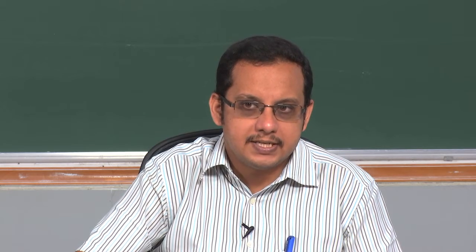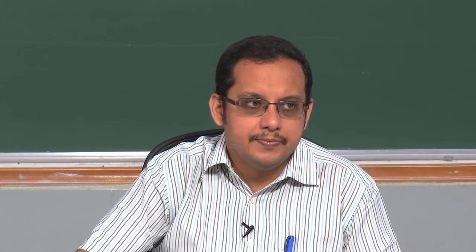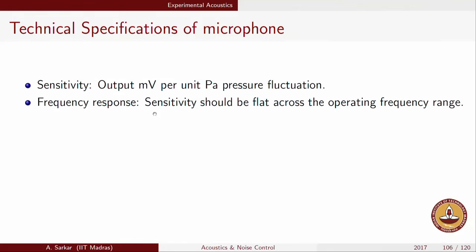Sensitivity is one of the most important factors in selecting a microphone. You need a high sensitivity value, because if the voltage is very low it will be embedded in the electrical noise of your measuring system and will not be properly manifested. Higher voltage gives good signal quality, so higher sensitivity is what is called for in applications.